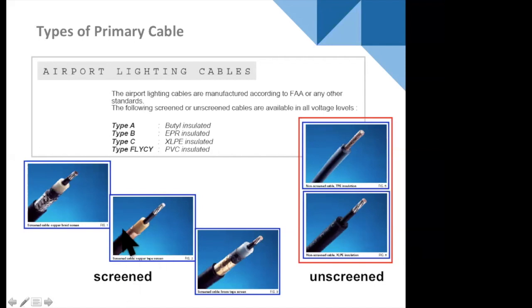But there are two types. There's screen cable. That means it has a screen of some material. And there's unscreened cable. In the ICAO world, we tend to use screen cable. In the FAA world, unscreened cable. And so there are differences. Certainly there are going to be differences in the installation, because when we use unscreened cable, it's very important that we have an earthing network called a counterpoise earthing network for lightning protection, especially in areas where there is the potential of electrical storms. So with unscreened cable, we have additional earthing cables installed, whereas in the ICAO world with screen cable, we may or may not have the additional earthing cable, the counterpoise earthing cable for lightning protection.